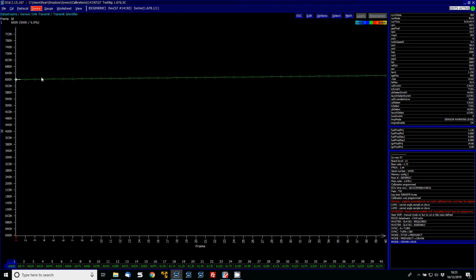Now the transmit identifier. The identifier values in here are basically just the default values used by a lot of external companies for our custom CAN protocol, so it's probably best not to use these. What I'd actually generally recommend is leaving the frames here from 0 to 20 alone, and doing the side of things right at the other end of the transmit identifier, keeping it separated from the actual main generic custom CAN transmit we have.